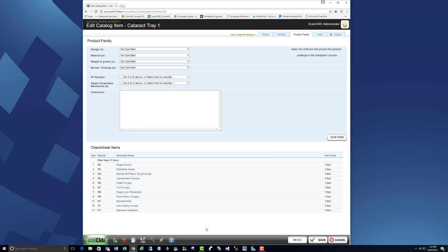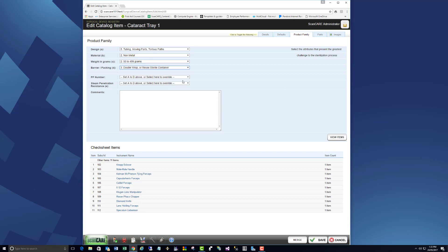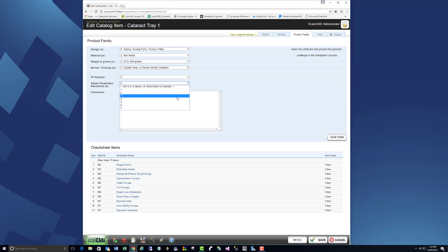The algorithm used to attribute product families to RMDs has been further developed, linking product families with steam penetration resistance. Product family and steam penetration resistance values can be modified to suit your own requirements.